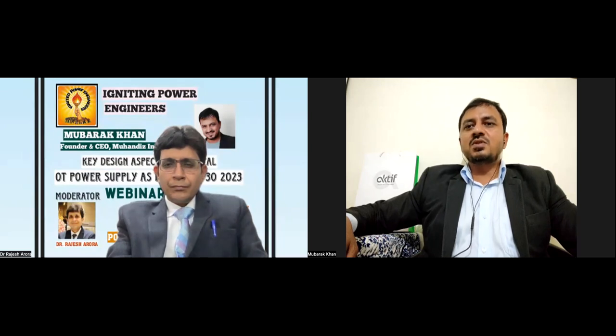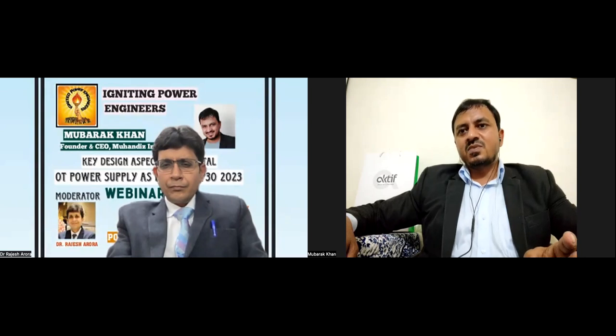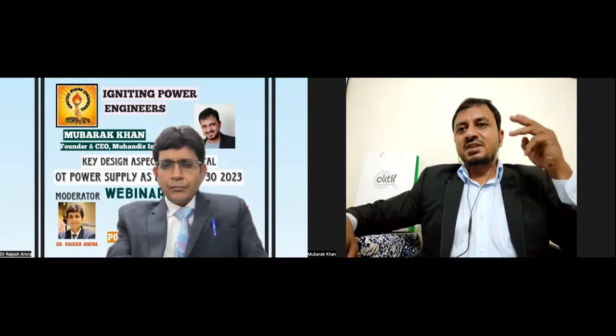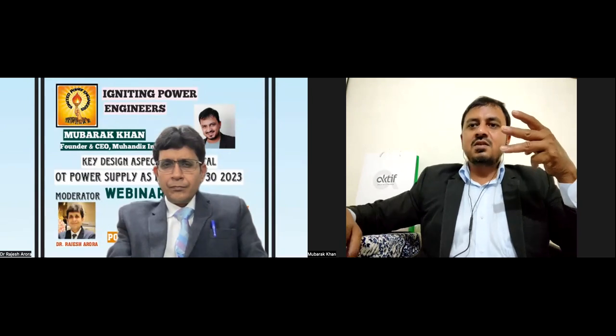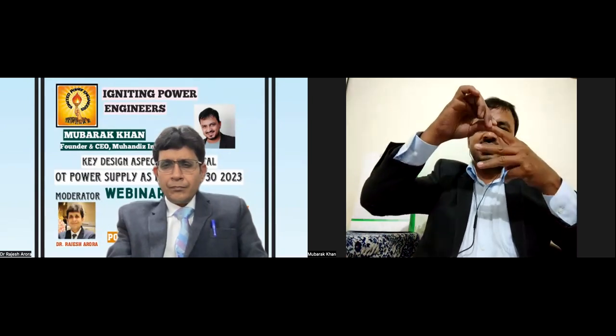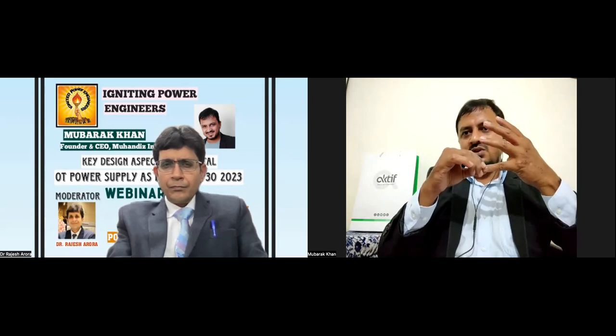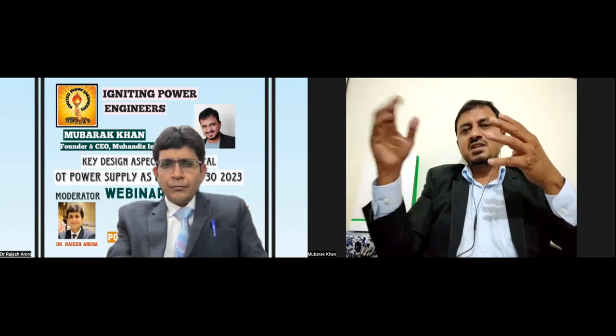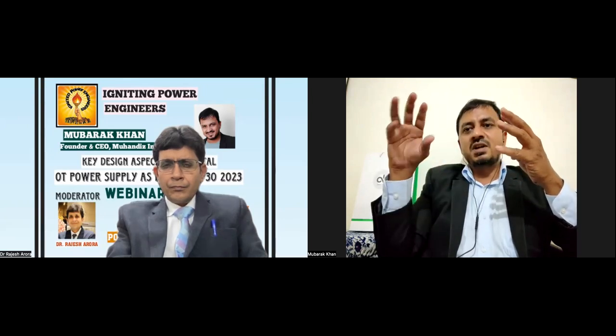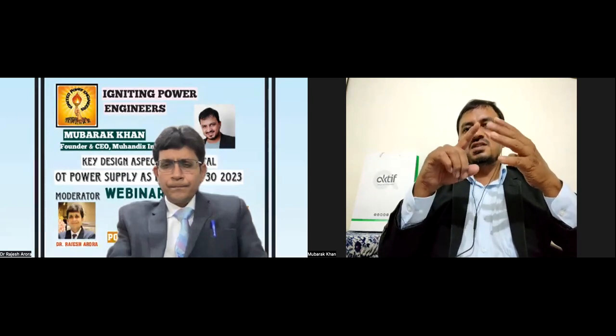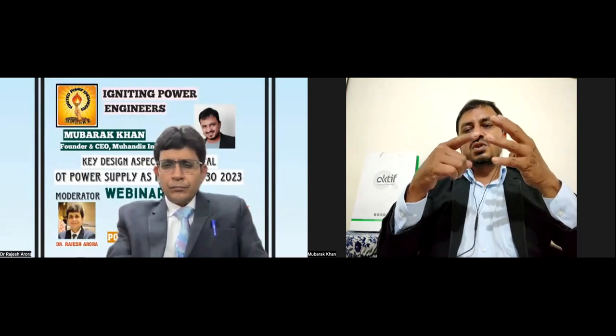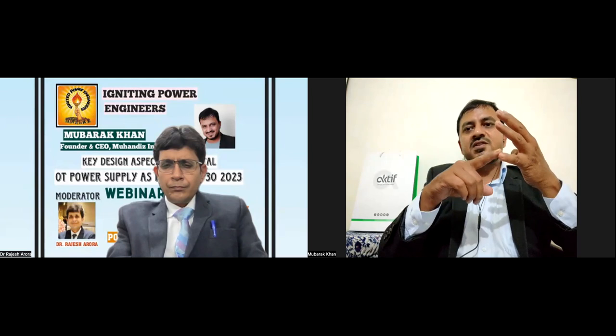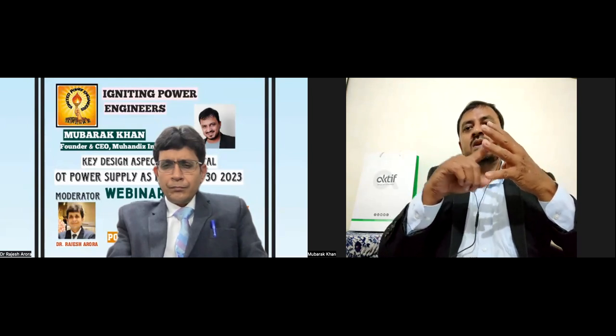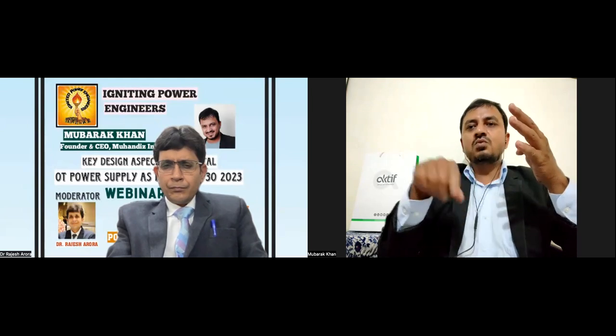The first thing is that you can load as much as you want, depending on the capacity of the transformer. The only thing is that all 3 phases must be loaded equally. Second, from a 3-phase supply, to use single phase we use phase and neutral. We don't need to convert 3-phase to single phase. Suppose there is a complex with A wing, B wing, C wing. When the transformer supplies power to this building, it gives one phase to A wing, one phase to B wing, one phase to C wing, and it distributes the neutral to all 3 buildings.